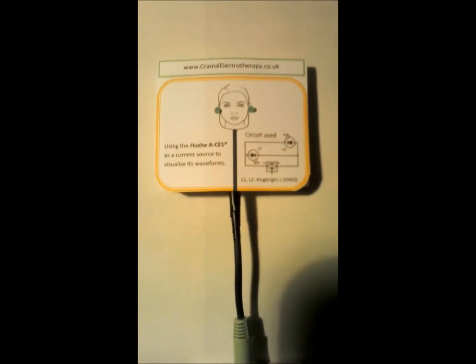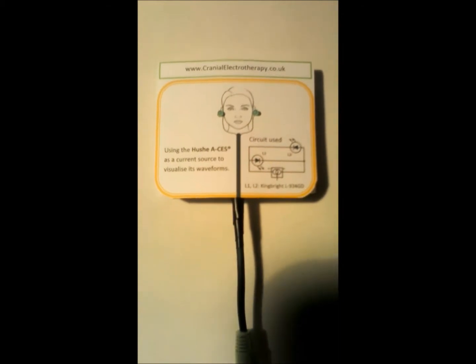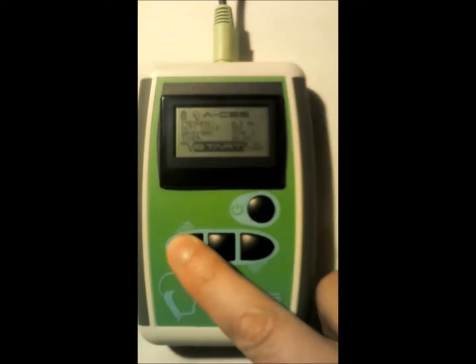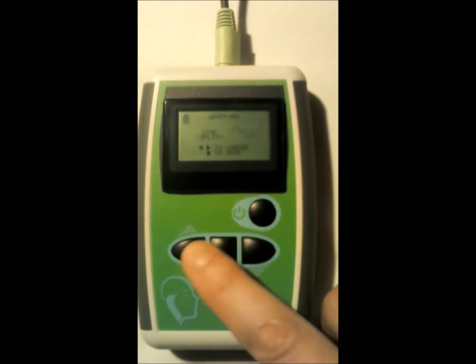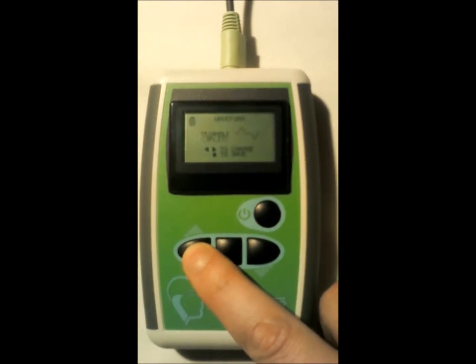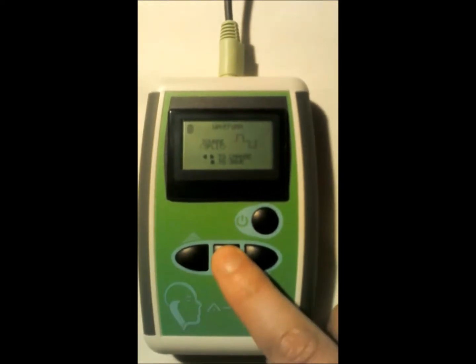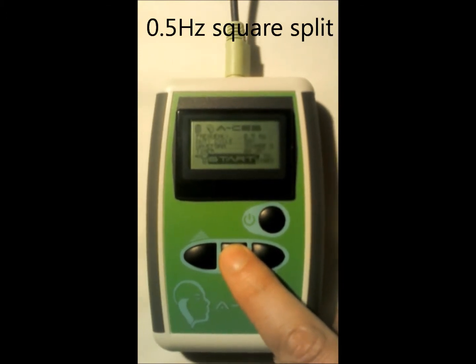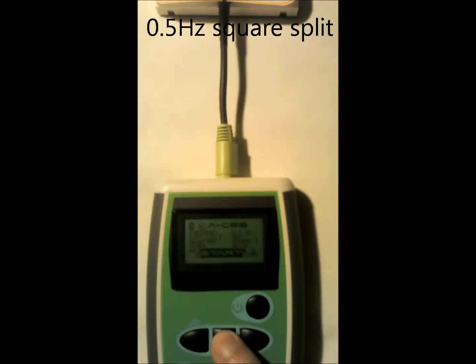As you can see, I've connected a demonstration circuit to the electrode jack socket on the Hushe A-CES, and the lighting shown by the LEDs should give you an idea of the low currents involved, together with an indication of the shape of the waveforms. The first waveform that I'll be demonstrating is a 0.5 Hz square split wave. I set the A-CES running at level 1.